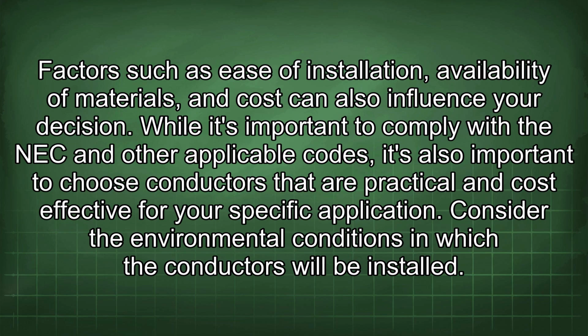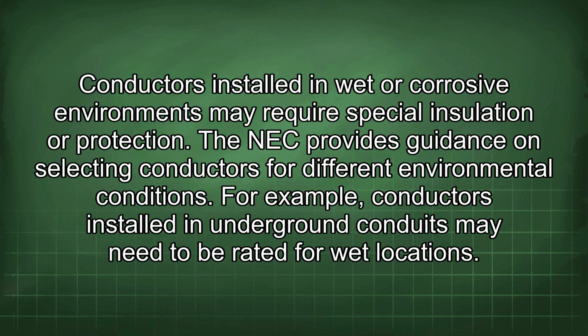Consider the environmental conditions in which the conductors will be installed. Conductors installed in wet or corrosive environments may require special insulation or protection. The NEC provides guidance on selecting conductors for different environmental conditions. For example, conductors installed in underground conduits may need to be rated for wet locations.